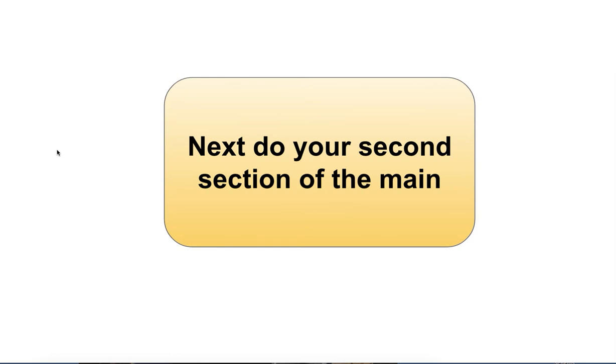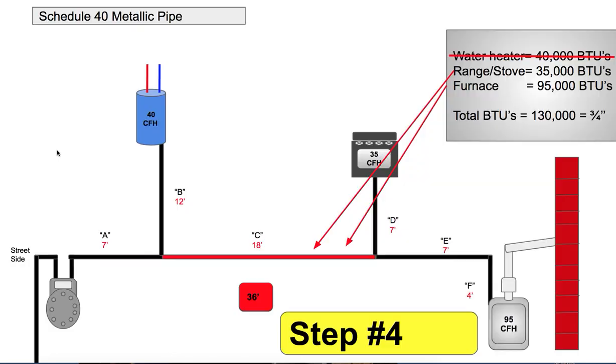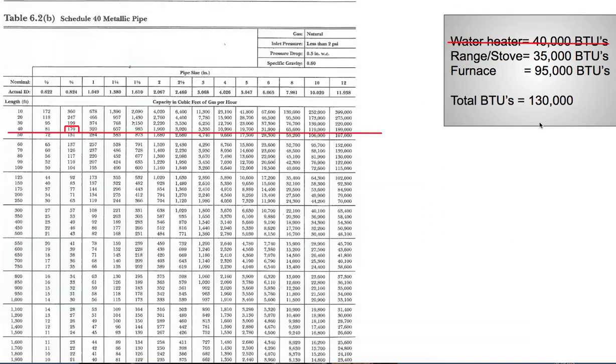Next, the second section of the main carries the load of the range and the furnace, which gives you 130,000 BTUs. In the 40-foot column, 130,000 is larger than 81,000, so that section is 3/4 inch.